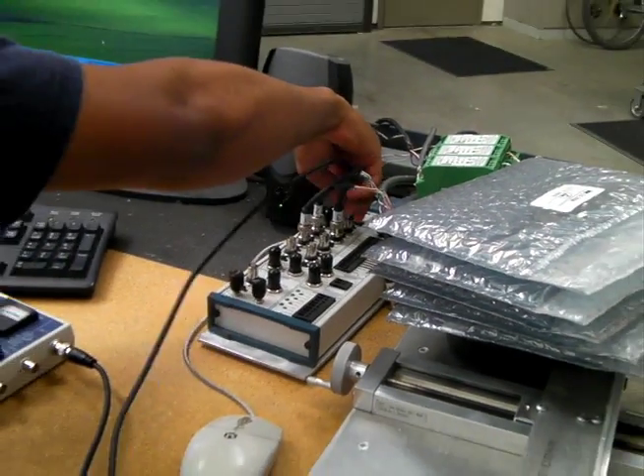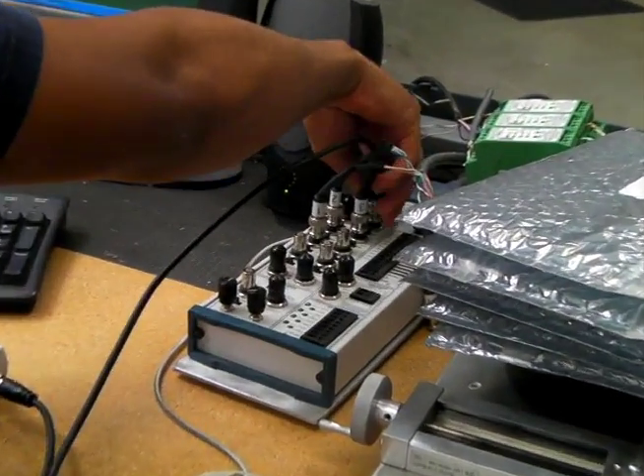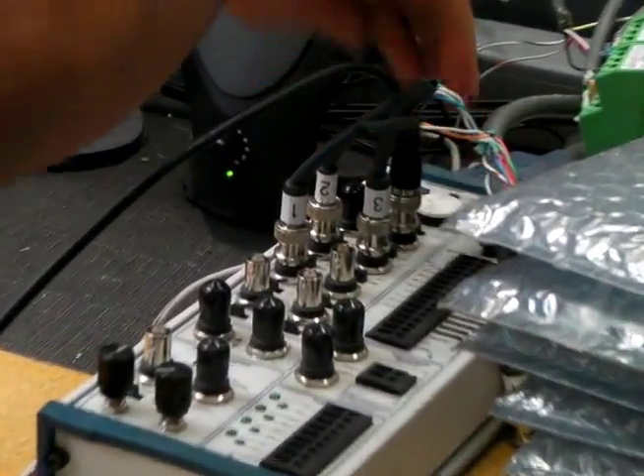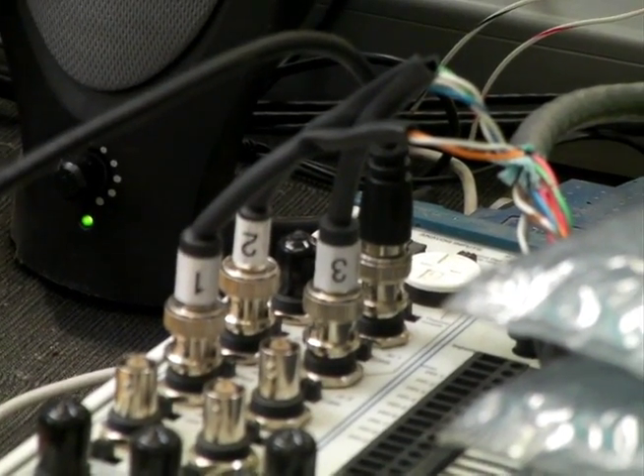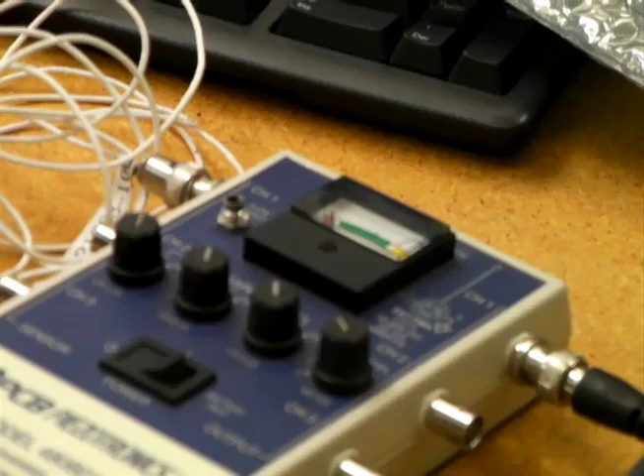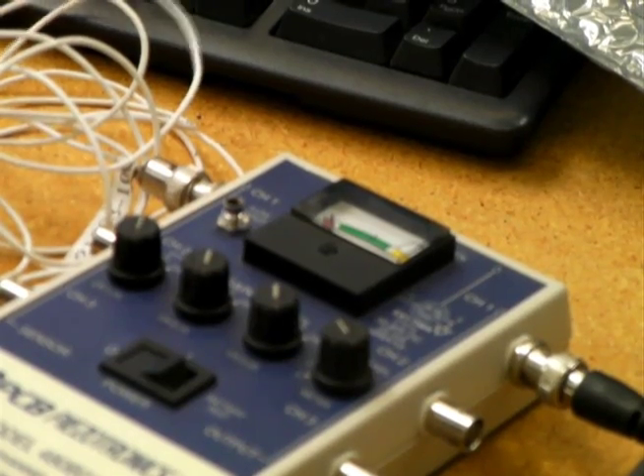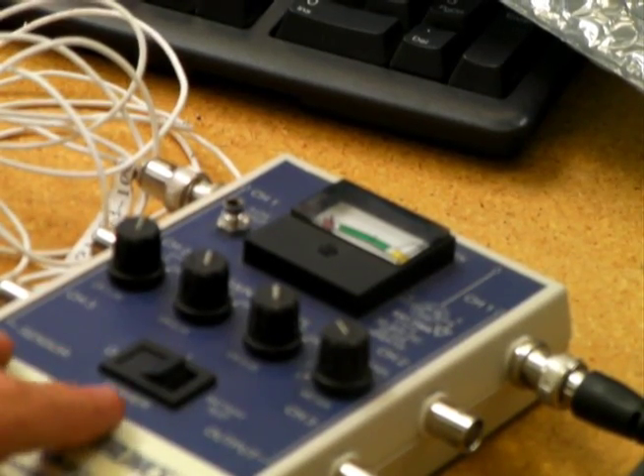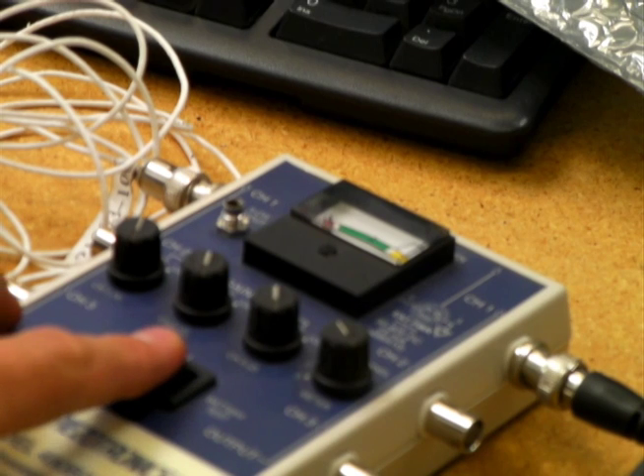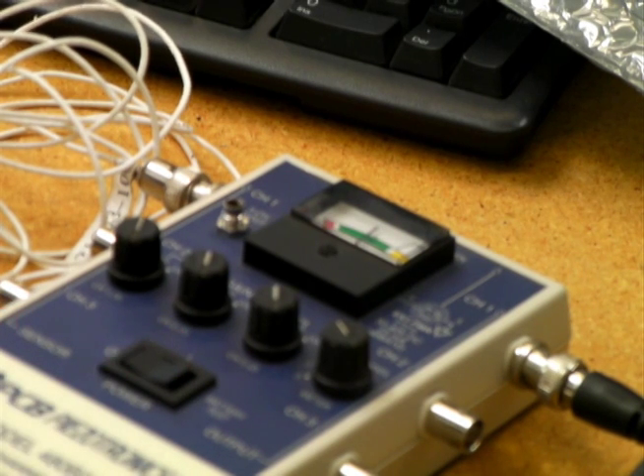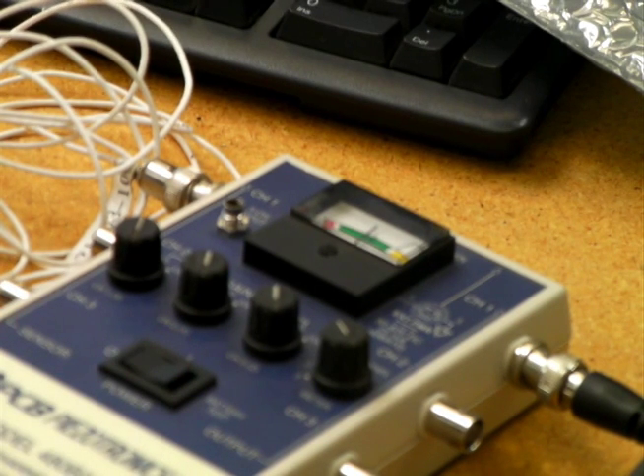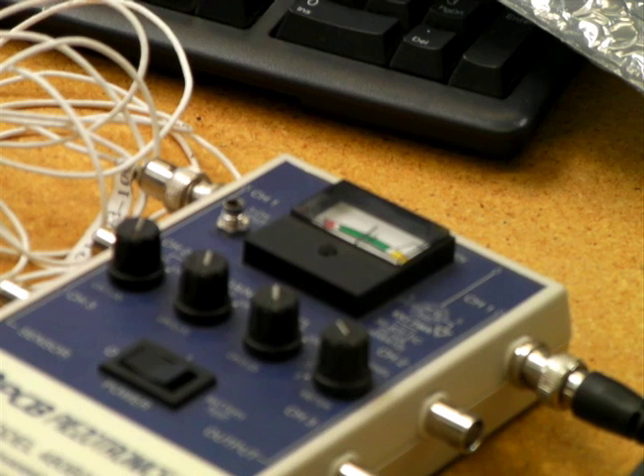To check your signal conditioner's battery power, first plug in your accelerometer to the top left jack of the conditioner. Then click the power button in the middle to check if the gauge lies in the green. If it lies in the red or yellow there is a problem and you should consult one of our associates.